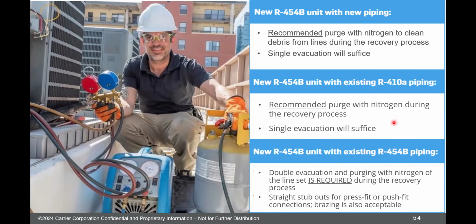In fact, I didn't know this until 13 months ago, but Carrier actually does not permit the use of RX11 flush. Those RX11 flush kits aren't allowed by Carrier. The tech support group here at TEC has informed me more than 10 times to tell people that that is not allowed by Carrier. We cannot use RX11 flush on R410A or 454B. I know people do. I know we sell it at the counter. I get it, but it's not something that's approved for use. And you don't need it, especially in this case, because it's the same oil. It's not even an issue there.